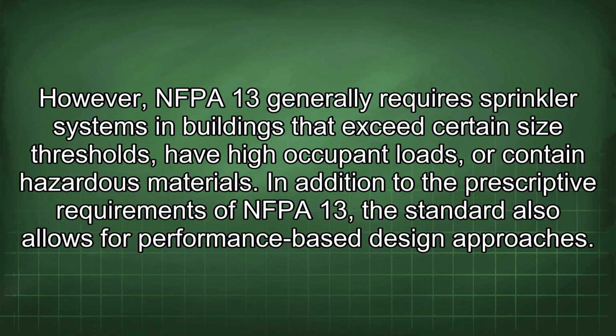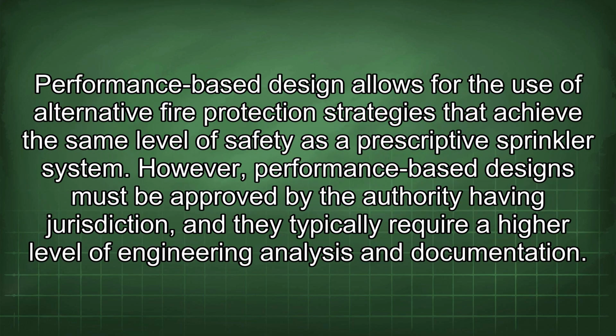In addition to the prescriptive requirements of NFPA 13, the standard also allows for performance-based design approaches. Performance-based design allows for the use of alternative fire protection strategies that achieve the same level of safety as a prescriptive sprinkler system. However, performance-based designs must be approved by the authority having jurisdiction, and they typically require a higher level of engineering analysis and documentation.